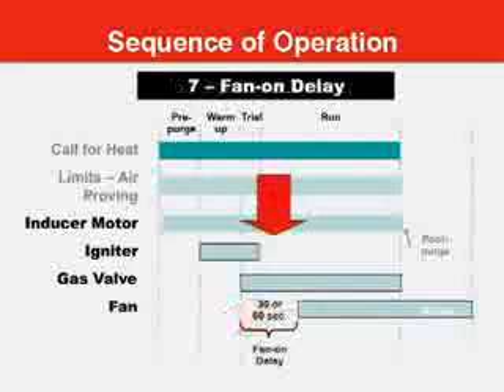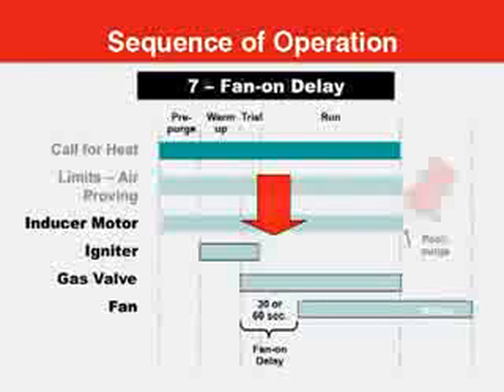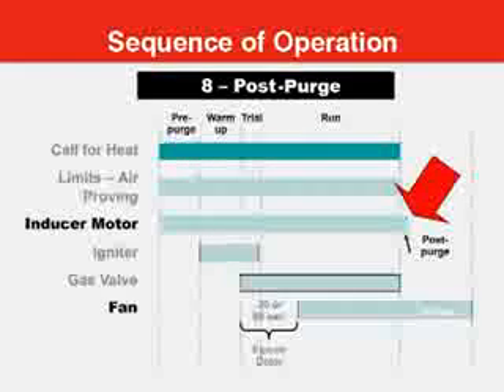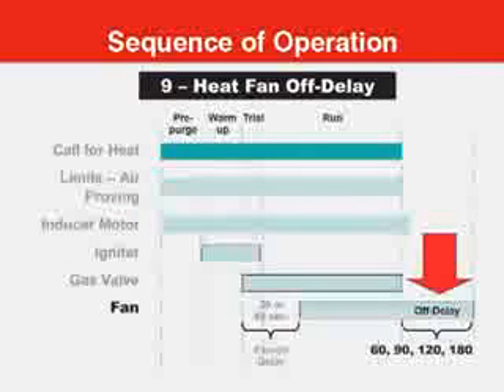At the same time the valve opens, the 30 or 60-second fan on delay starts. If the burner flame is not detected on the first trial, 2 more tries will be made before the control goes into a 1-hour soft lockout. At the end of the call for heat, the gas valve is de-energized and there's a 15-second post-purge during which the inducer fan continues to run. The heating fan off delay can be set to 60, 90, 120, or 180 seconds when the control is installed, or at any point after installation, in order to improve comfort. For cooling, there's an automatic 5-second cooling fan on delay and the choice of a 0 or 60-second fan off delay. Let me show you up close where all these adjustments and connections are.